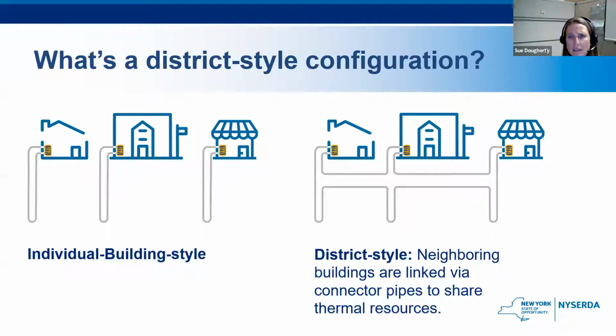I talked about this briefly in the last slide. What we're talking about with district-style heat pump systems, or thermal energy networks, is networking a cluster of buildings together with pipes so we can share thermal resources. On the left, each building is using ground source heat pumps to heat and cool. But we have reason to believe, and evidence to support, that connecting these buildings together lets us achieve heating and cooling more efficiently. One building might be in cooling mode while another is in heating mode, so heat rejected from the building in cooling mode could be used by another building. By connecting these buildings together, they can also share the same thermal resources.